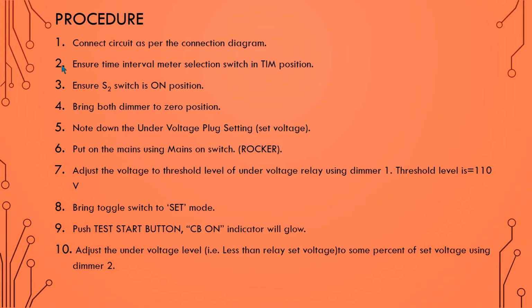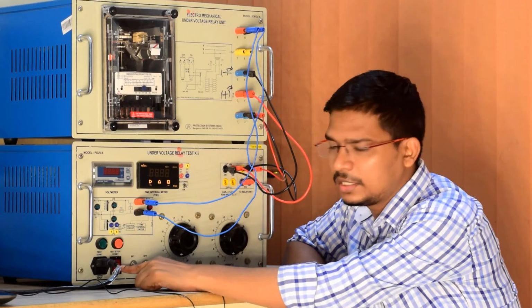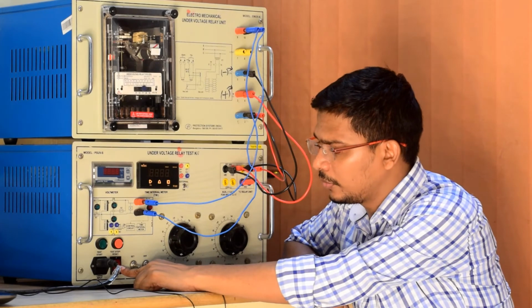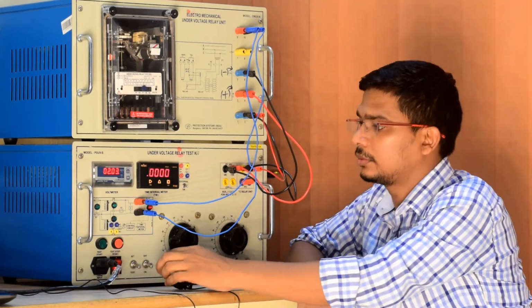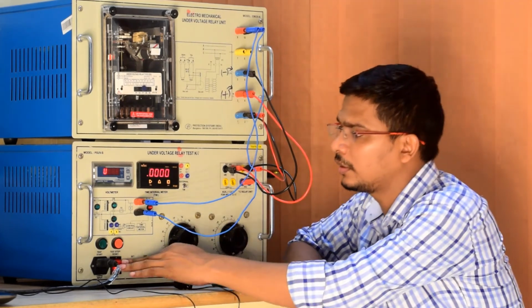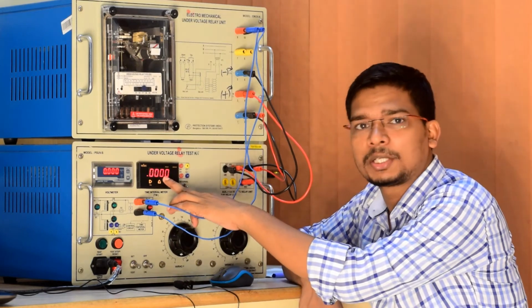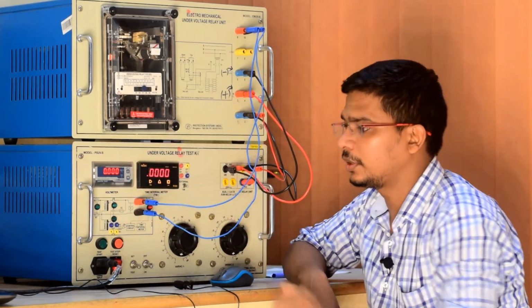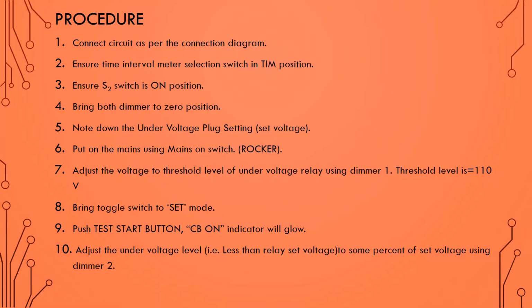So what is the next procedure? Put on the mains using mains on rocker switch. So as you can see, this is the mains on rocker switch. So we have to put it on. So this is turning on. After turning on, you can see the display of the time interval meter is showing and the display of the voltmeter is also showing. And the next process is to adjust the voltage to the threshold level of the under voltage relay using dimmer 1. And the threshold level is 110 volt.